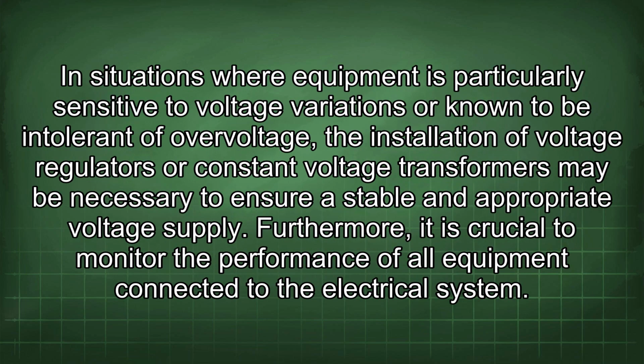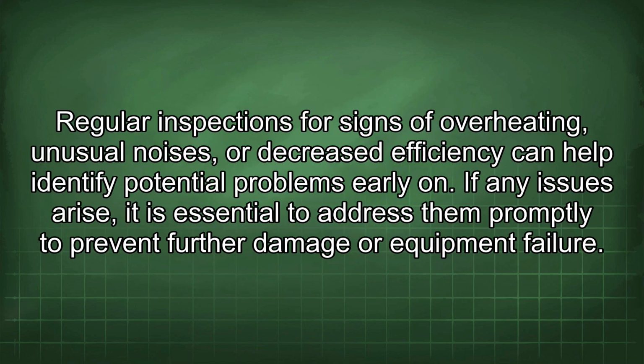In situations where equipment is particularly sensitive to voltage variations or known to be intolerant of overvoltage, the installation of voltage regulators or constant voltage transformers may be necessary to ensure a stable and appropriate voltage supply. Furthermore, it is crucial to monitor the performance of all equipment connected to the electrical system. Regular inspections for signs of overheating, unusual noises, or decreased efficiency can help identify potential problems early on. If any issues arise, it is essential to address them promptly to prevent further damage or equipment failure.